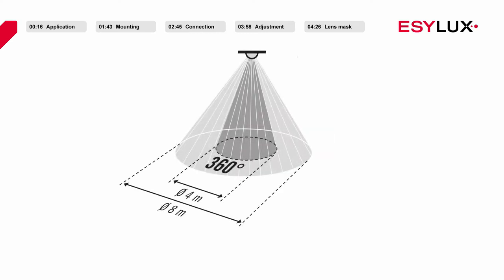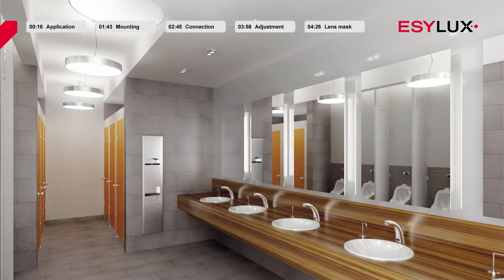Both products have a 360 degree field of detection. At the recommended installation height of 2.5 to 3 meters, the detection range of both products covers a diameter of 8 meters. ESYLUX ceiling mounted motion detectors are developed and produced in Germany. They are especially well suited to small rooms and passageways that receive a very low level of natural daylight.